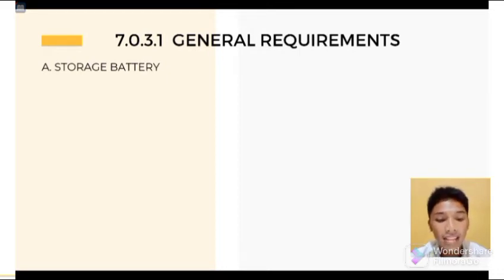Batteries, whether of the acid or alkali type, shall be designed and constructed to meet the requirements of emergency service and shall be compatible with the charger for the particular installation. For a sealed battery naman, the container shall not be required to be transparent. Okay, so take note of that. For the sealed battery, it is not required for it to be transparent. However, for the lead acid battery that requires water additions, transparent or translucent jars shall be furnished.